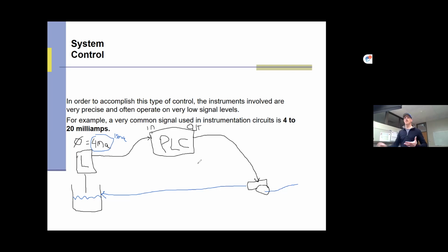You can really be complex with your PLC. You can say, I want to hold the level in that tank at 15 milliamps. If it changes at all, I want you to compensate, pump more or pump less using, say, a variable frequency drive or some sort of drive that will provide more or less water if you need it. And those are things that are a little bit more complex in your PLC, but they all run on the 4 to 20 milliamp scale.